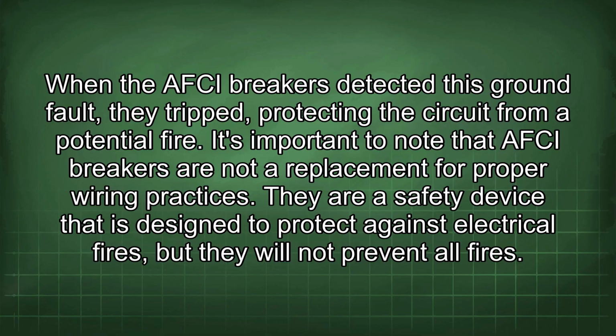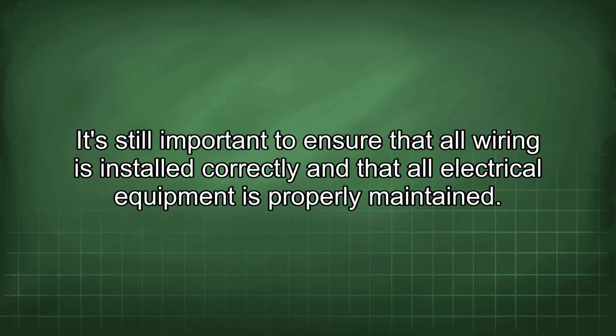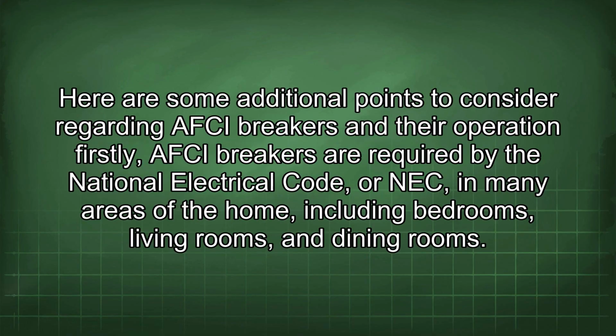It's important to note that AFCI breakers are not a replacement for proper wiring practices. They are a safety device that is designed to protect against electrical fires, but they will not prevent all fires. It's still important to ensure that all wiring is installed correctly and that all electrical equipment is properly maintained. Here are some additional points to consider regarding AFCI breakers and their operation. Firstly, AFCI breakers are required by the National Electrical Code, or NEC, in many areas of the home, including bedrooms, living rooms, and dining rooms.